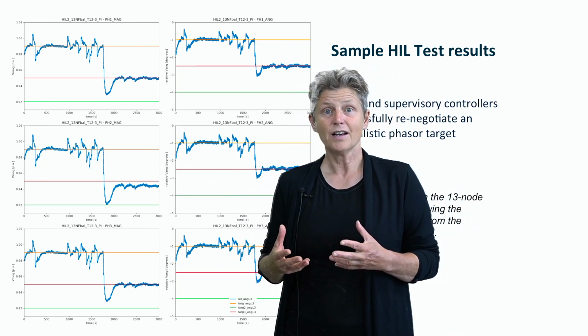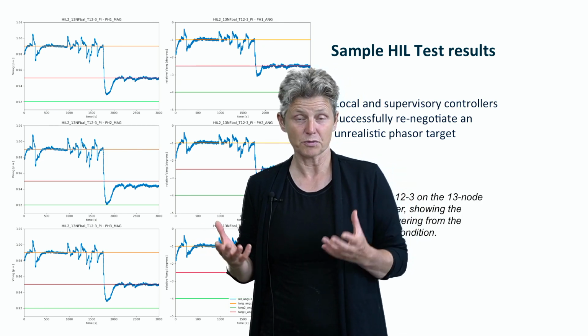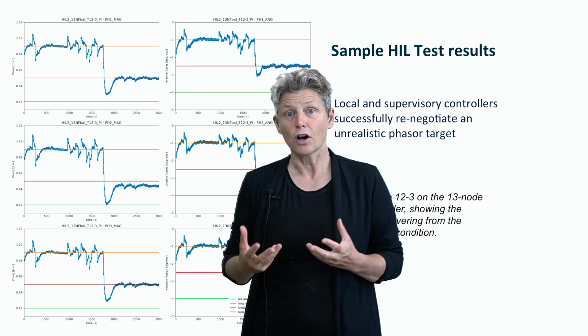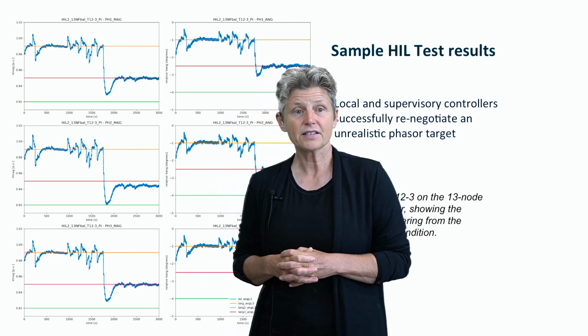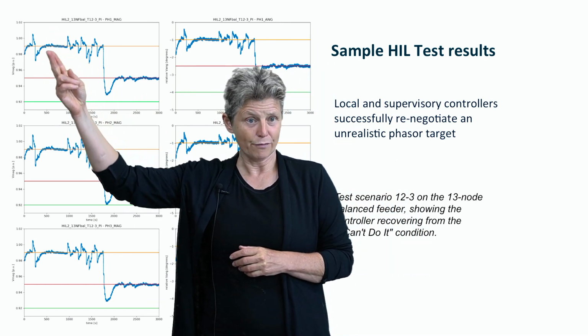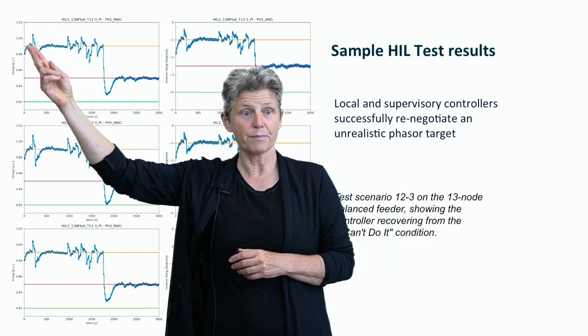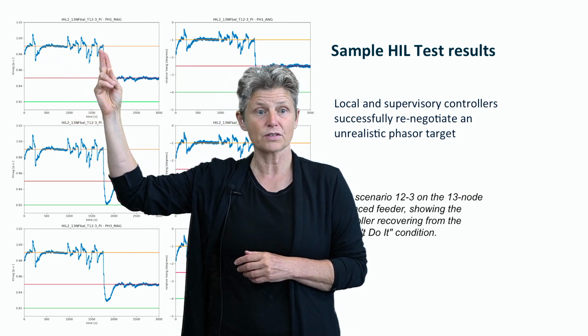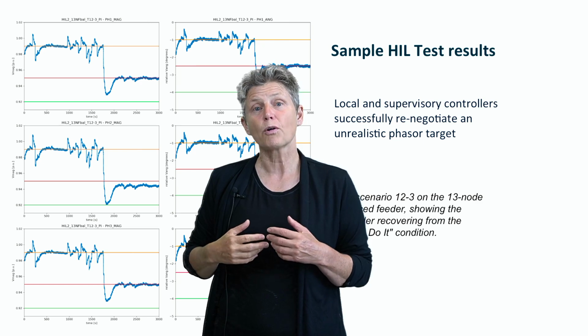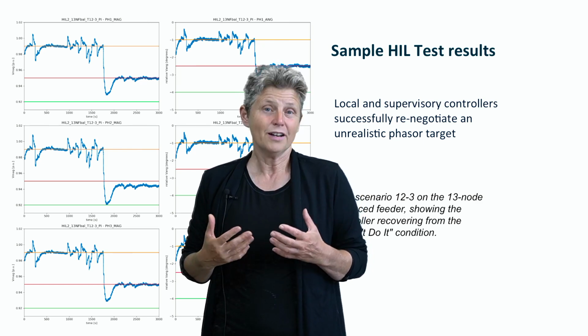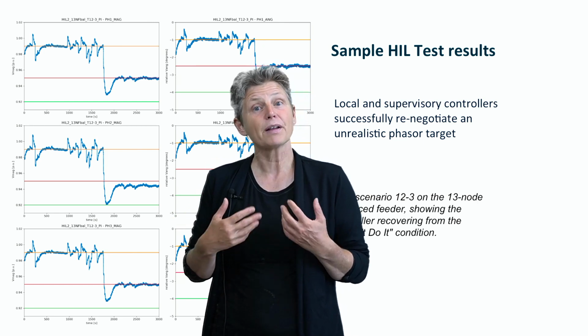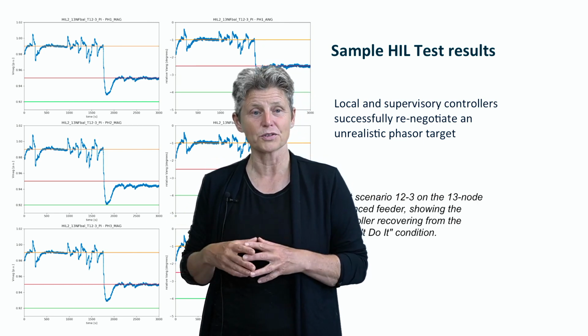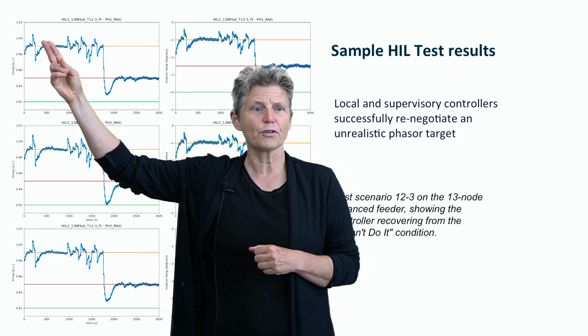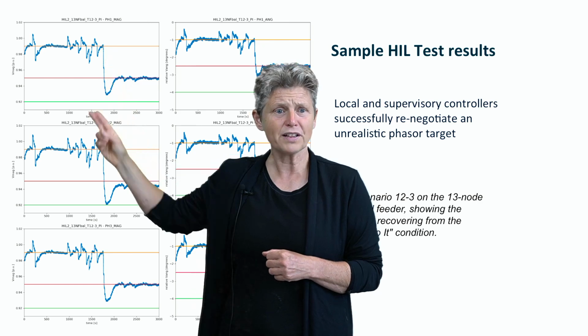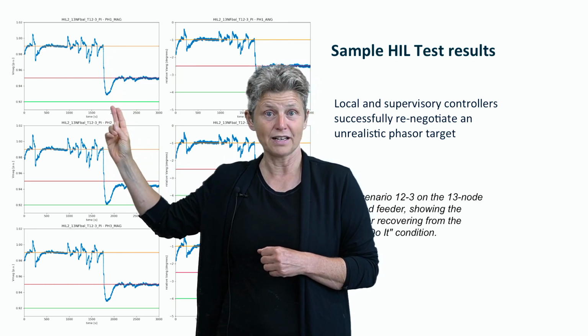Now, you may wonder what happens if the supervisory controller issues targets that are physically infeasible for the actuators to respond to. And the answer is, well, they talk to each other and negotiate a little bit. So in this example, we have disturbances that are being rejected. The target value is this yellow line. And then the supervisory controller makes a really radical jump, which in real life we wouldn't want it to do, but this is for stress testing the whole control setup. So it says, well, instead of 0.99 per unit, I want you to bring the voltage down to 0.92, which is this green line.